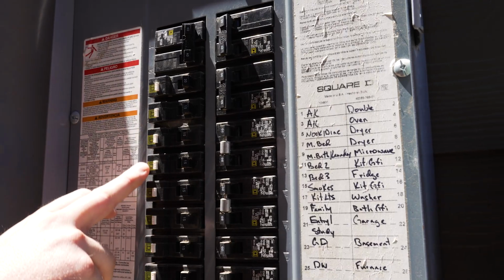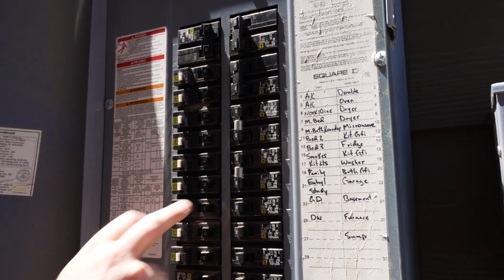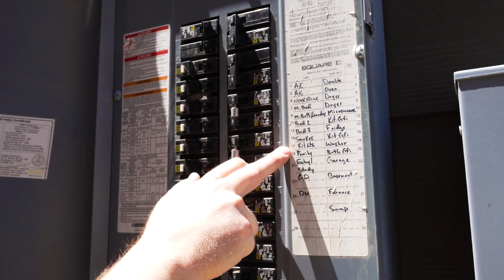You have one circuit breaker that takes power to, say, the bedroom. We always want one breaker, one wire bringing power into that room. Double tap is two wires essentially going to two separate areas, maybe one going into that bedroom and another into the master bedroom. Two separate areas sharing the same amount of power is not a good idea. You plug in a vacuum cleaner and it trips the breaker frequently, that tells you something's wrong, because you probably have a double tapped wire.